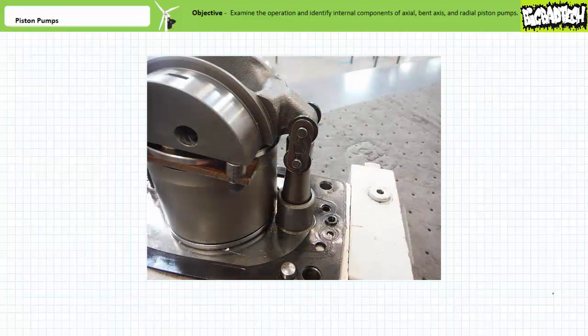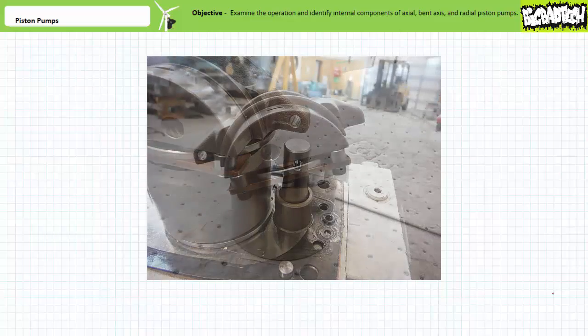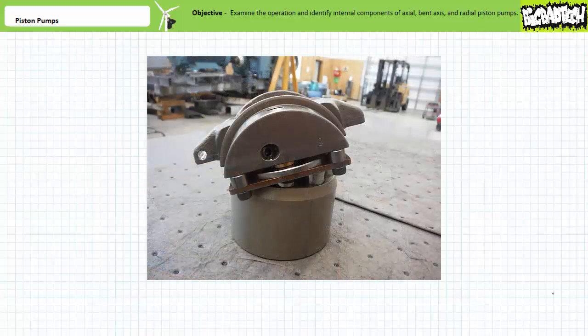The swashplate is linked to a movable piston and features the other half of the rocker mechanism. As the piston linked to the swashplate extends and retracts, the angle of the swashplate changes, making this a variable displacement axial piston pump. We can remove the mechanical linkage and then remove the piston block, pistons, and swashplate. We can now see how the angle of the swashplate affects displacement value per revolution.